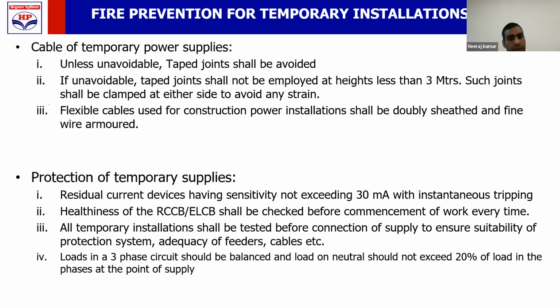The cable shall be flexible type, but will have mechanical protection by means of double sheath and fine wire armor. Not the main armor जो हमारा पावर केबल में आता है, fine wire armor. इसको normal terms में बोलते हैं braided cable. So the cables from the main switch to the temporary supply shall be braided cable. Supply to the main switch will be armored cable.